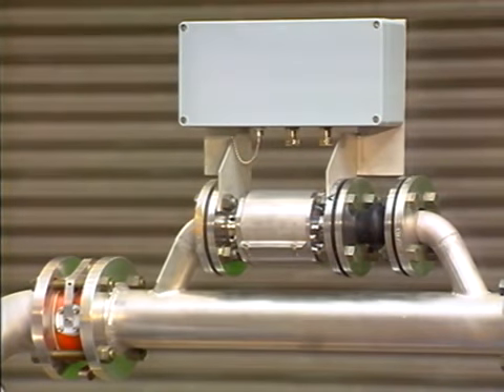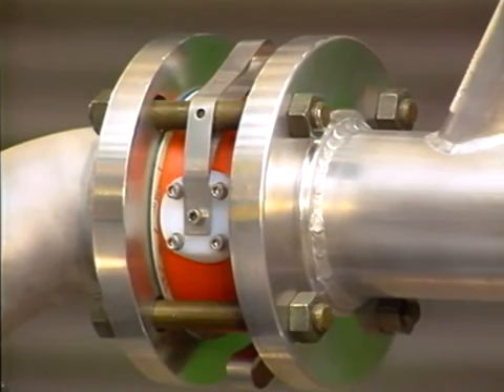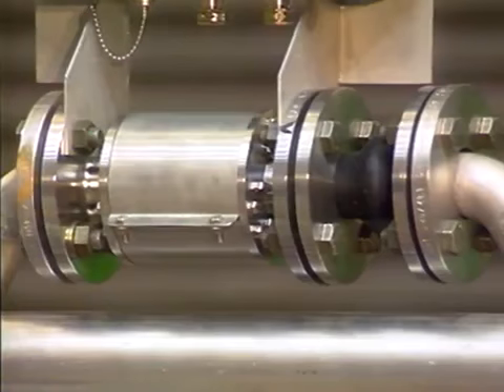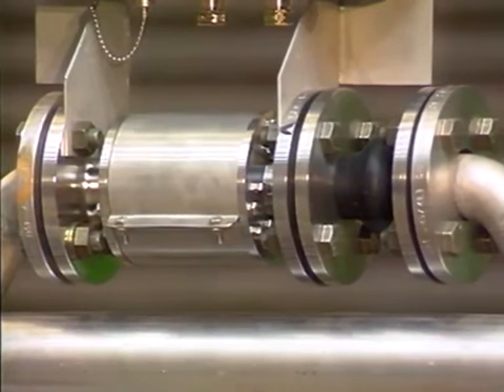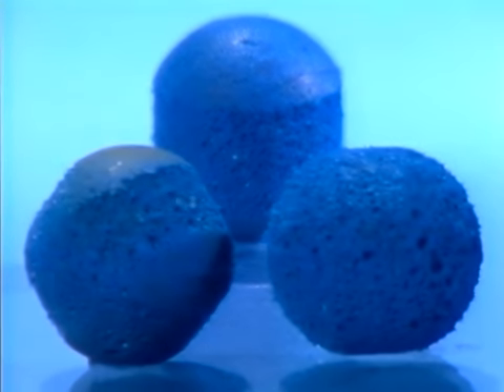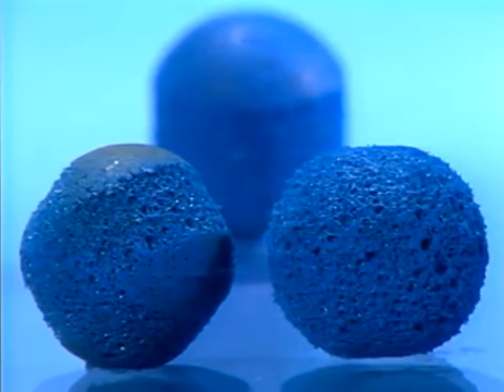Depending on the degree of automation, the ball recirculating unit can be equipped with special monitoring devices. The BRM monitors the number of balls, while the BOM measures the degree of wear and thus actual ball size. Given the conditions, the ball life can last up to 6 weeks. Balls, downsized through wear to the diameter of the tubes, lose all their cleaning capability.